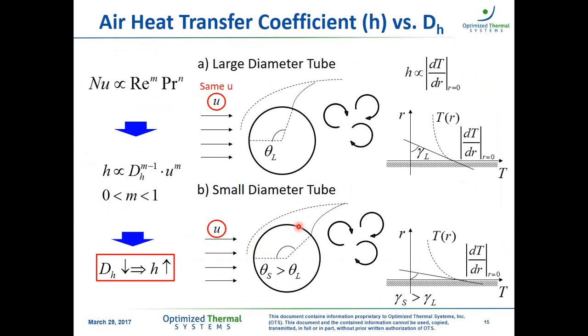Another interesting aspect of this is that since we have the same velocity, the Reynolds number on a small diameter tube is smaller. Therefore, the separation point occurs a little bit further along the surface. So we have a relatively larger effective heat transfer surface on a small diameter tube compared to the larger diameter. And why are we comparing same velocities? Because in the heat exchanger context, we usually have similar face areas and similar flow rates. So the actual airflow velocity across the tube bundle is very similar regardless of the tube diameter.